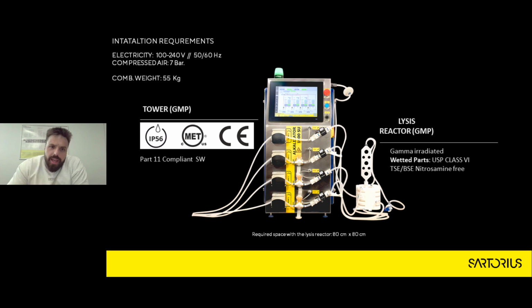So you're not adding that much. The combined weight of this machine and lysis reactor is approximately 55 kilograms. So it's not really heavy, not really small, it's more of a pilot size, and the required space is approximately 80 centimeters by 80 centimeters. So you can easily put it on a tabletop or on a trolley and use it when you need it, then just store it away.